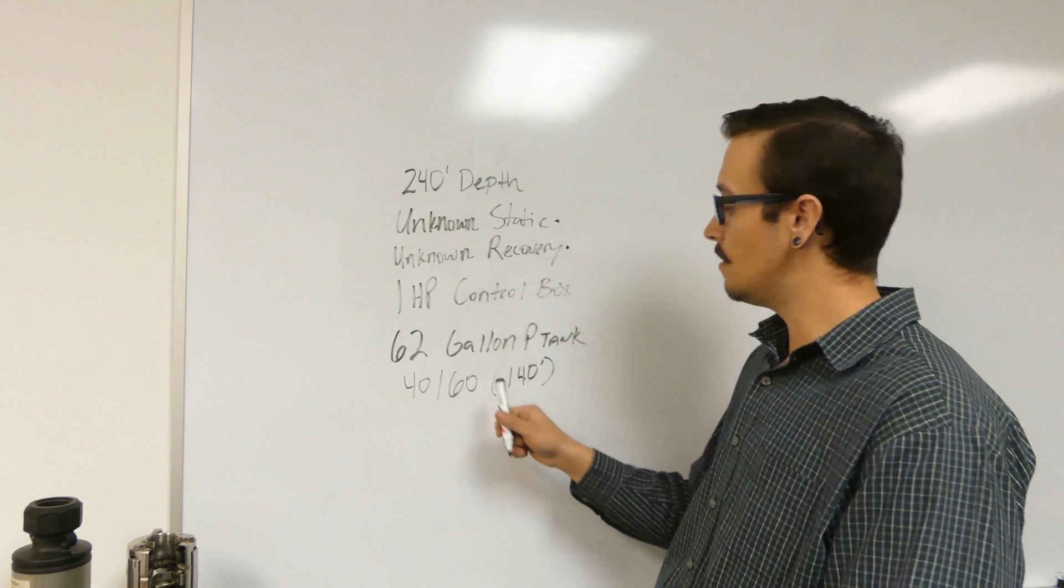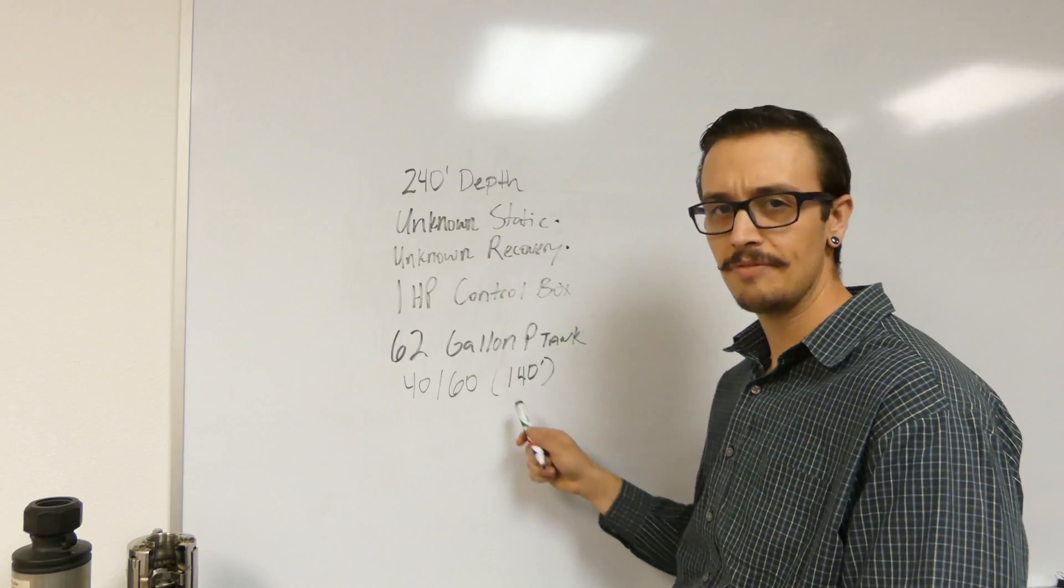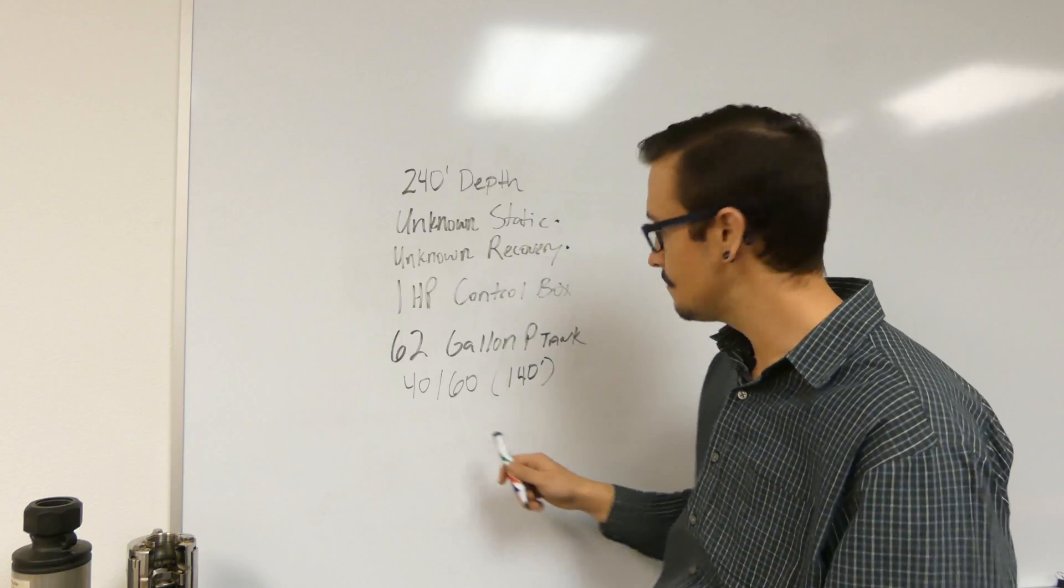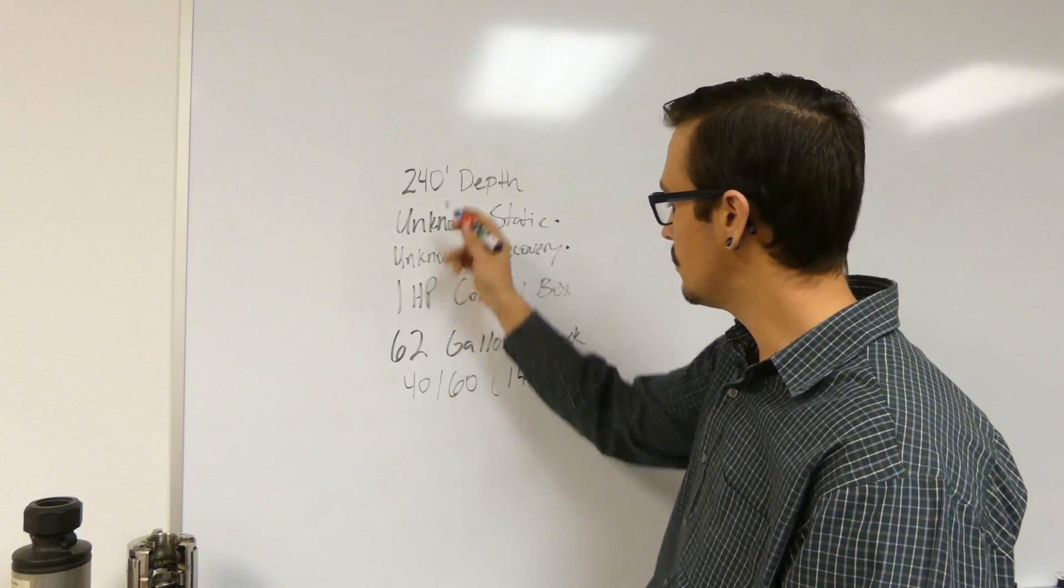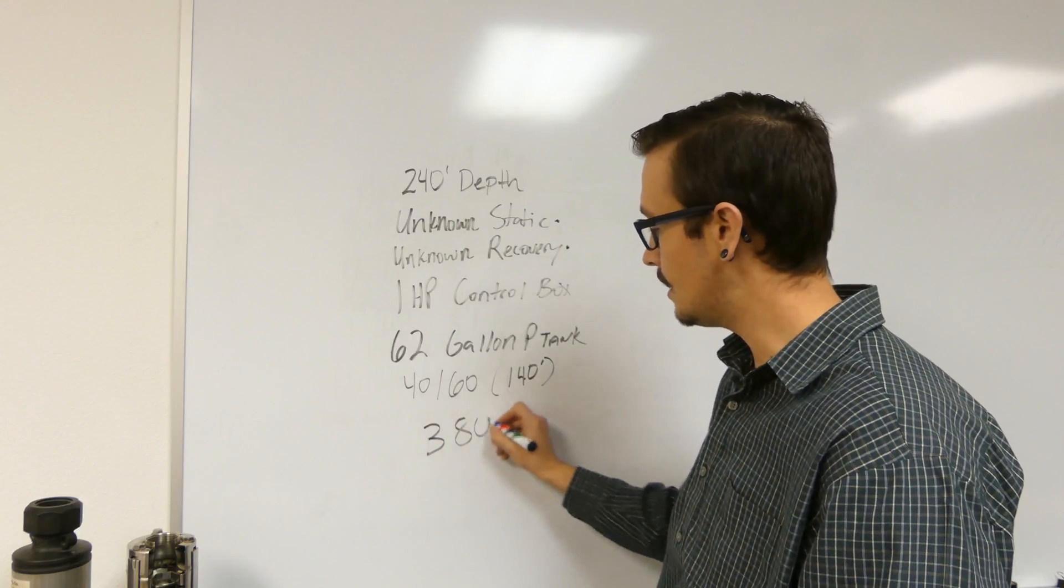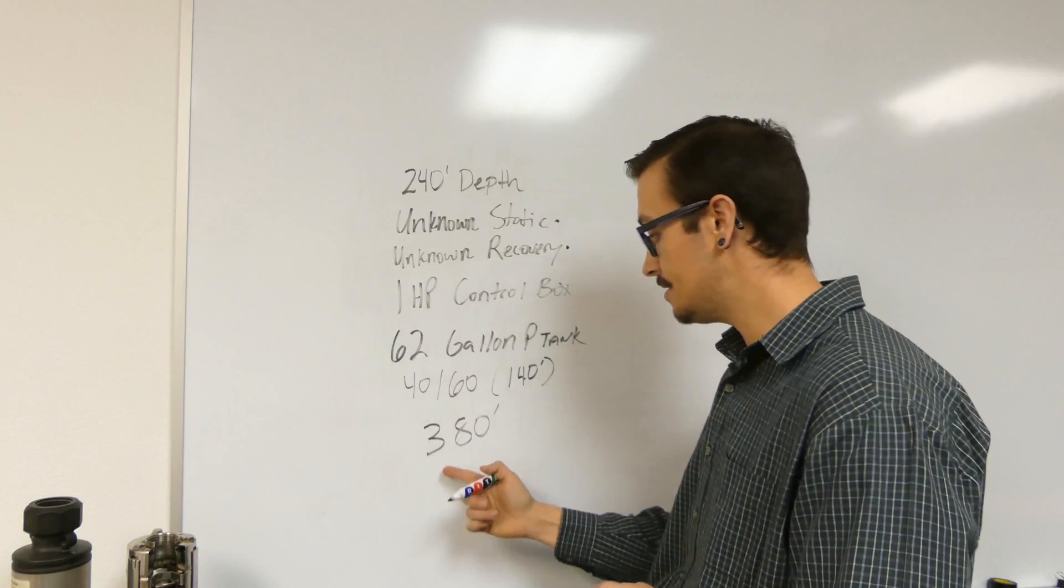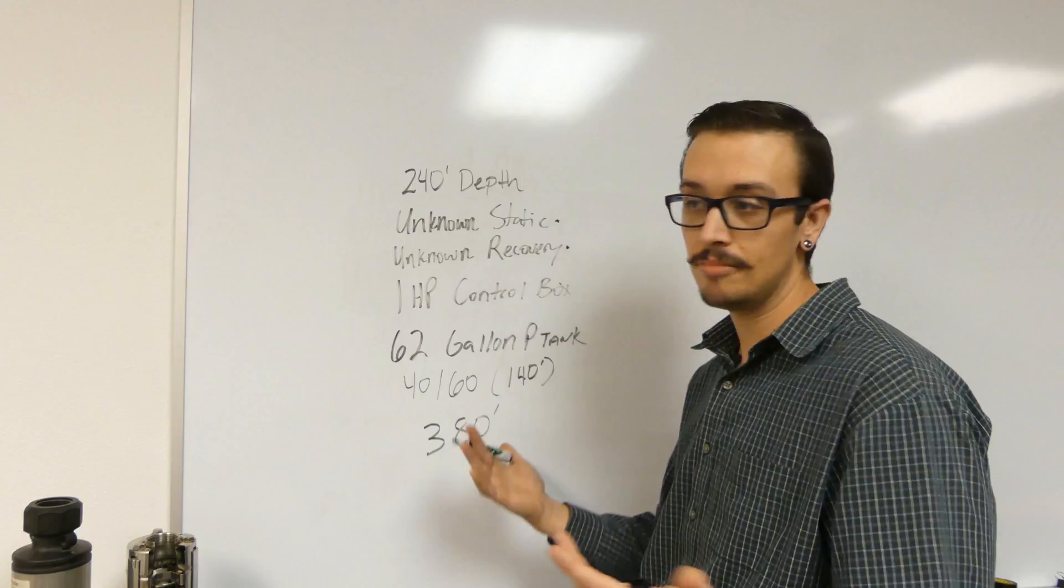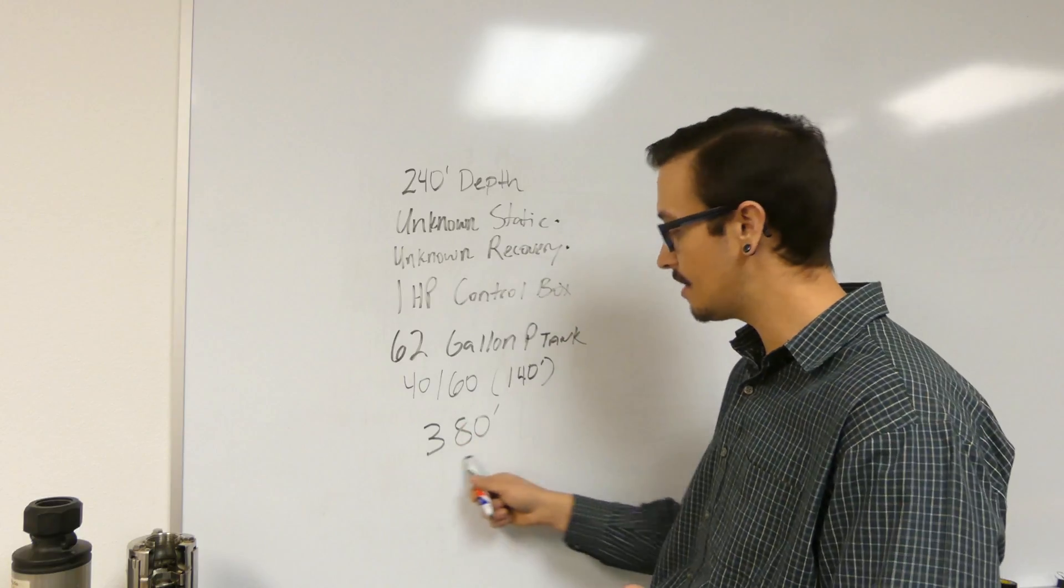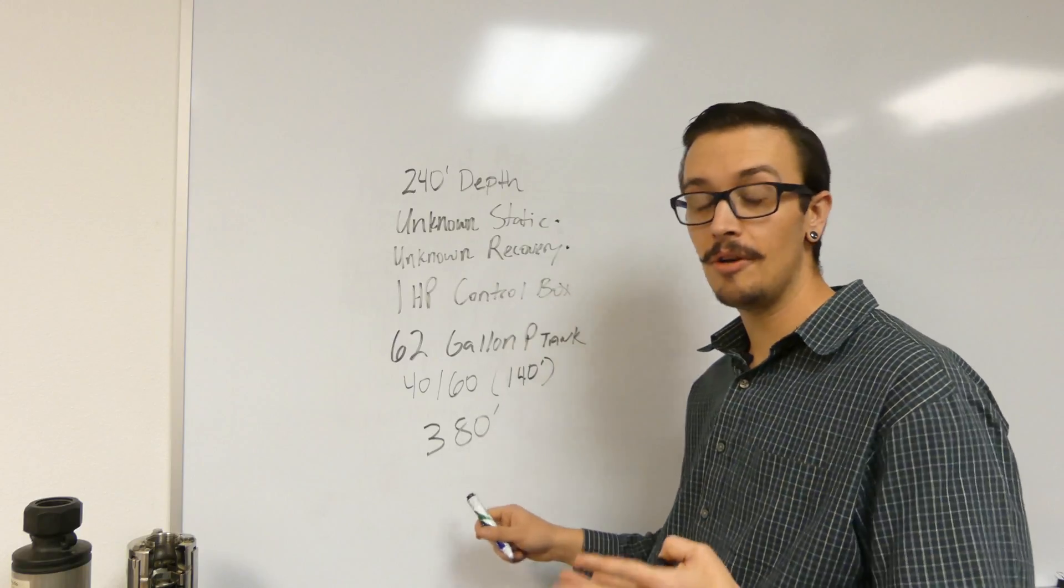Okay, so we've got 240 plus 140, and of course that factors for just a tiny bit of friction loss. So we total those up together, we're at 380. So that's pretty good. Now we've got at least our TDH or an example TDH figured out.